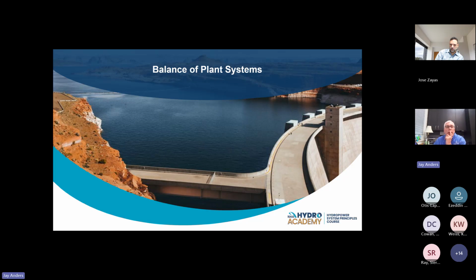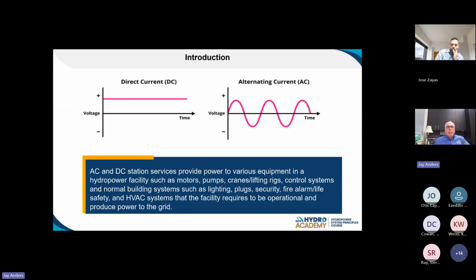I want to spend a few minutes talking about the balance of plant systems, particularly on the electrical side. As you guys get into the mechanicals and other systems, they'll get a lot more into that. But just on the balance of plant electrical systems, like I talked about, we have DC systems, direct current systems, battery systems at the plants, and also our alternating current systems. We have lots of security systems, fire protection, HVAC, heating, cooling, lighting, all kinds of stuff going on at these power plants that take internal power. These are loads we have to account for, loads we have to make sure are energized in the event of a failure. We need to make sure we have power available to keep all of our most important loads, the loads required for us to come back in a black start situation.